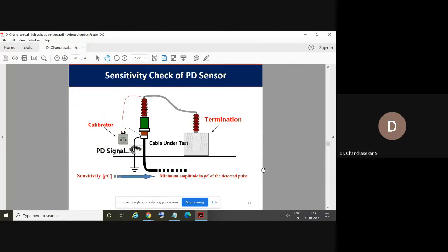Okay, so before starting the measurement, we need to have a calibrator. That calibrator is shown in this picture. It will inject known PD signals of a particular magnitude. We can set the magnitude of the signal we want to inject, and then using this calibrator, we need to inject that particular signal into the test equipment.